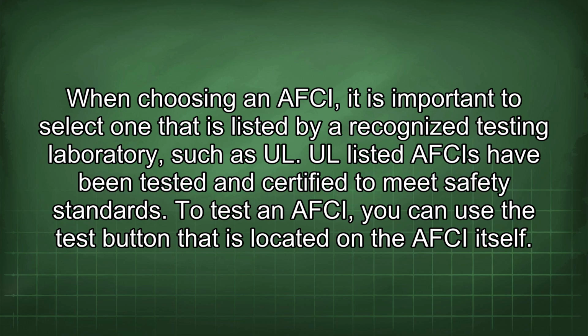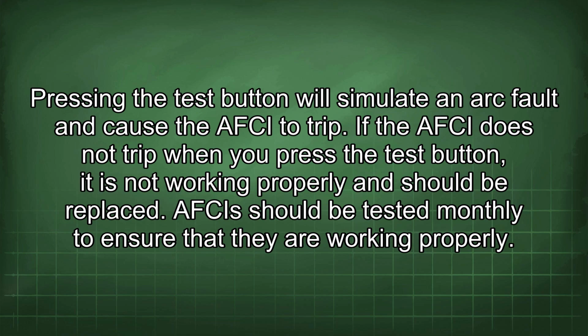To test an AFCI, you can use the test button that is located on the AFCI itself. Pressing the test button will simulate an arc fault and cause the AFCI to trip. If the AFCI does not trip when you press the test button, it is not working properly and should be replaced. AFCIs should be tested monthly to ensure that they are working properly.